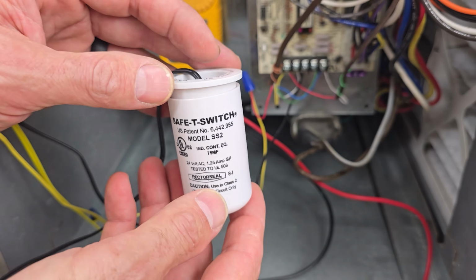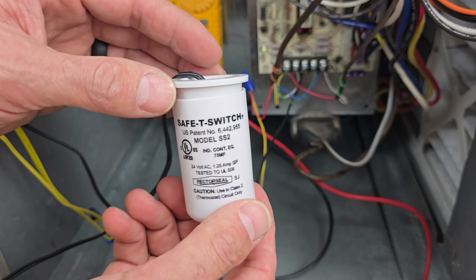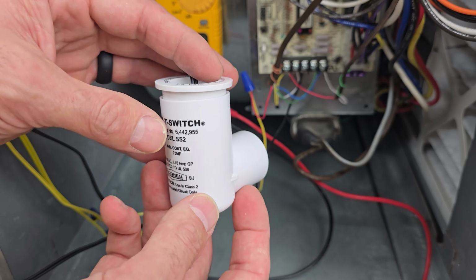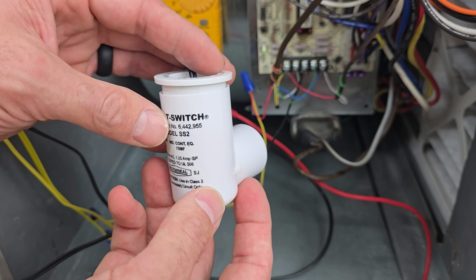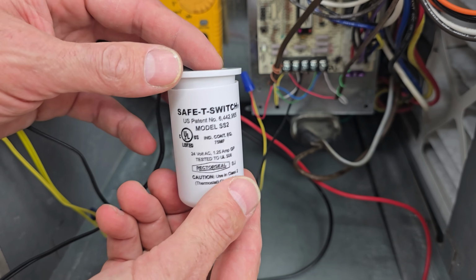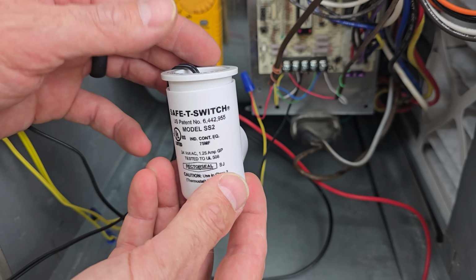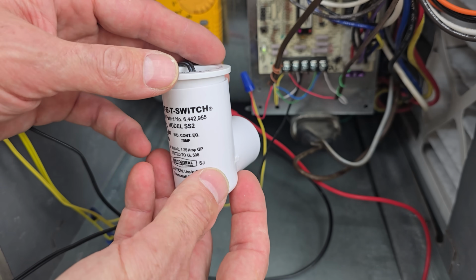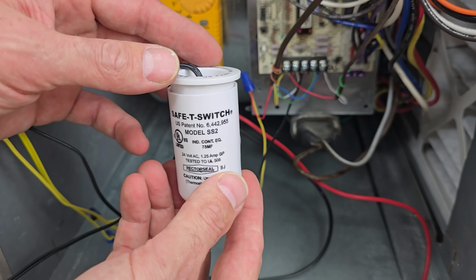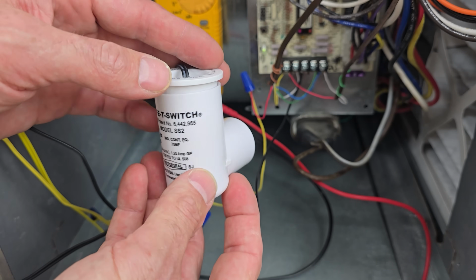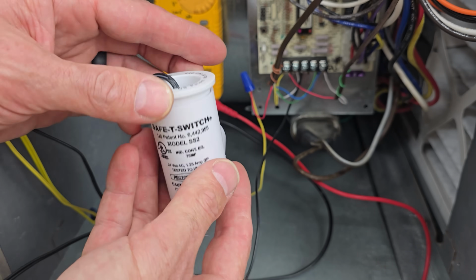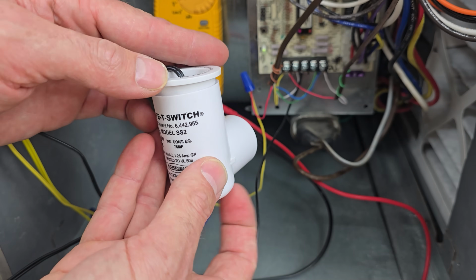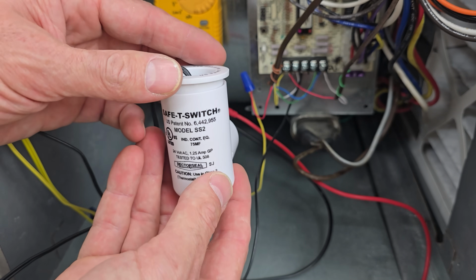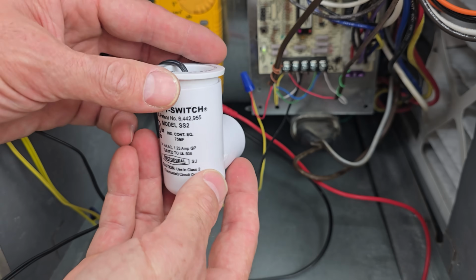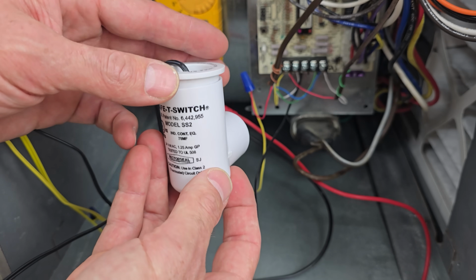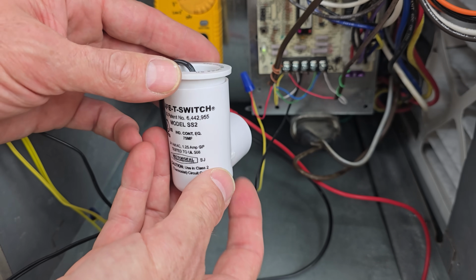Now remember that safety switch right here is a protection device to make sure you don't have the condensate overfilling the condensate pan due to a clog, which would create a lot of water damage within the furnace itself and within the building structure. So you want to make sure to clean out that condensate line properly. And once again, all these PVC fittings should be primed and glued while they're dry and have a chance to set before you turn, say, an air conditioning system on to run it.